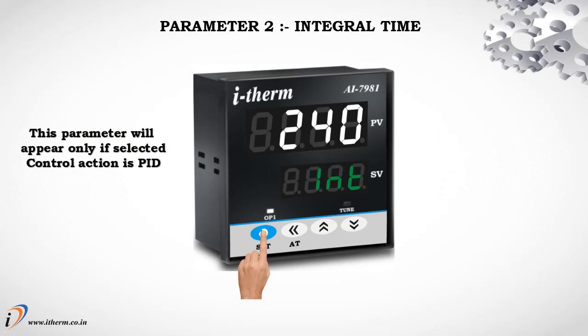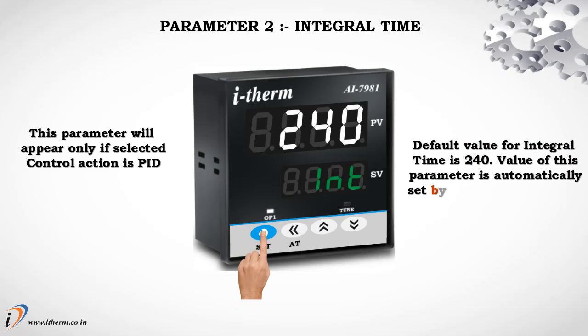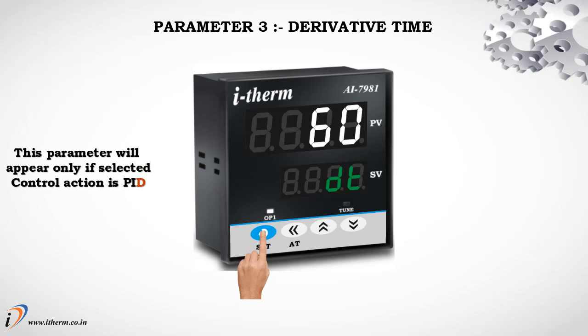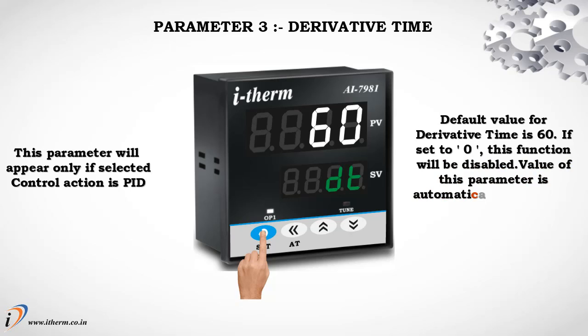This parameter is automatically set by auto tune function. Parameter 3: Derivative Time. This parameter will appear only if selected control action is PID. Default value for derivative time is 60. If set to 0, this function will be disabled. Value of this parameter is automatically set by auto tune function.